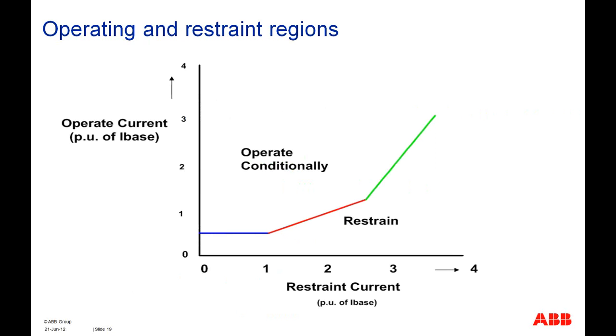So here is the operating and restraining characteristic. As you can see from here, the per unit operating current is on the y-axis, and on the x-axis we have the restraining current in per unit of I base, and the dual characteristic will look like this. Anything above this characteristic line would be the tripping area or operating area, and anything below this characteristic line would be the restraining area.